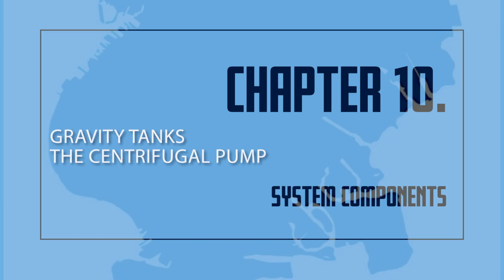The centrifugal pump. The centrifugal fire pump is the standard pump currently used in fire protection systems. This is the preferred pump because it is reliable, compact, requires low maintenance, and it can be powered by a variety of drivers including electric motors, internal combustion engines, and steam turbines. Principle of operation. The water available to the centrifugal pump must always be under pressure because the pump cannot lift water from the supply source.